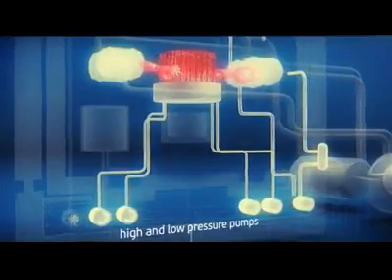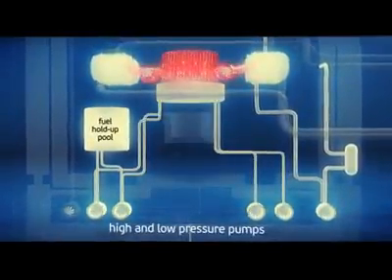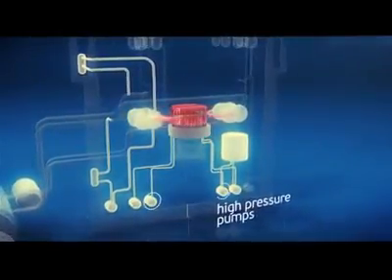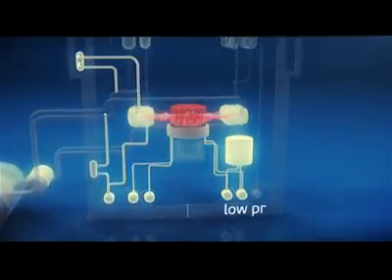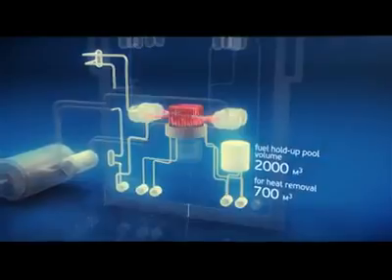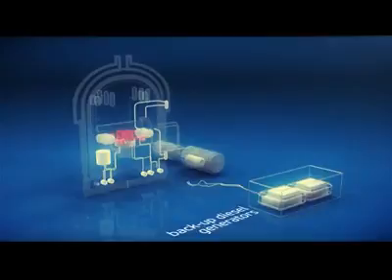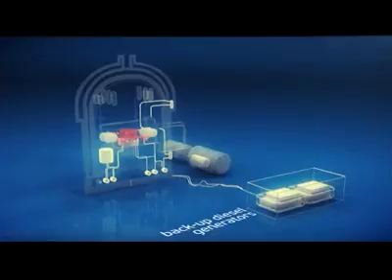If the leak is small and high pressure is maintained in the circuit, high-pressure pumps operate. If the leak is large — for instance in case of a pipeline break — and pressure is dropping, low-pressure pumps are engaged. The spent fuel hold-up pond is more than 2,000 cubic meters, of which 700 cubic meters can be used for heat removal of the primary circuit. Power supply of the active safety systems is independent owing to backup diesel generators which start automatically without human involvement in cases of power loss. Each unit with a VVER reactor includes four independent diesel generators located in different rooms to exclude a possible common cause of failure.